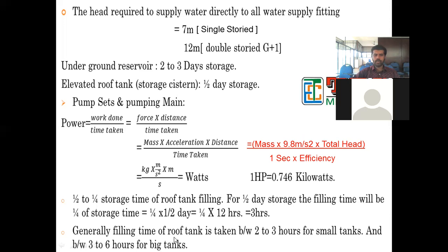So generally the filling time of roof tanks is taken between 2 to 3 hours for small tanks and between 3 to 6 hours for big tanks. These are the general criteria. So this also you have to keep in mind when we are trying to design it, we can decide what should be our storage time or what is the time taken to fill our overhead tank.